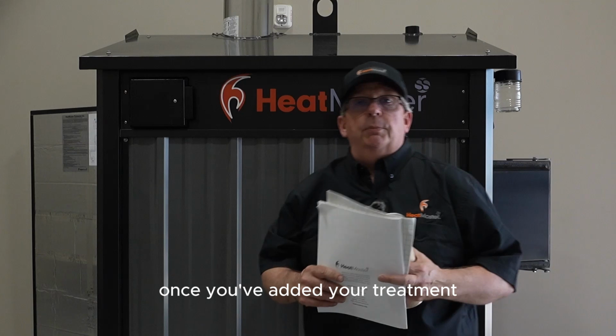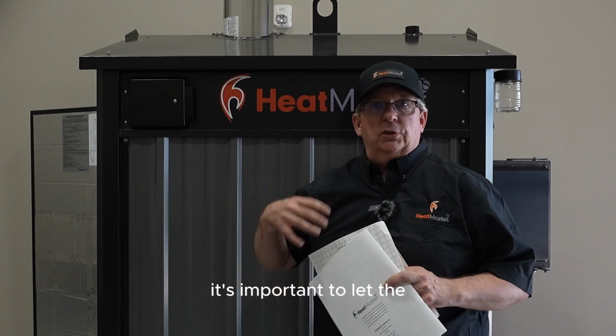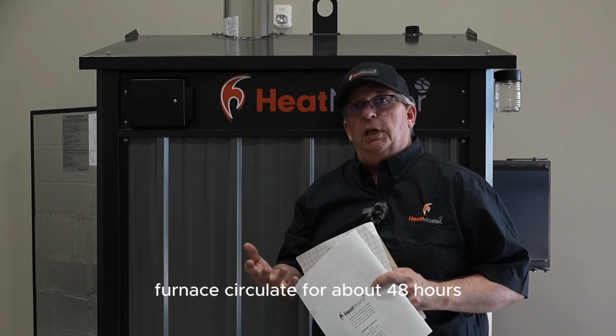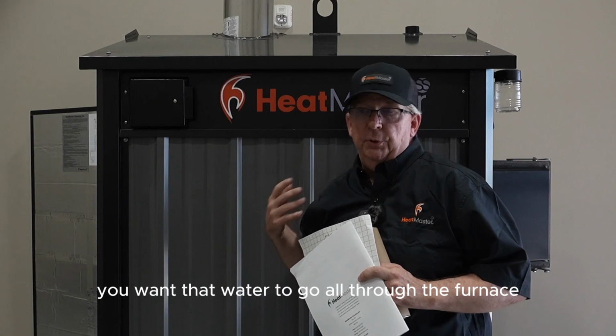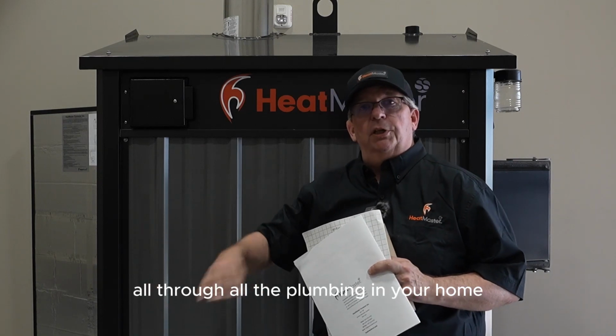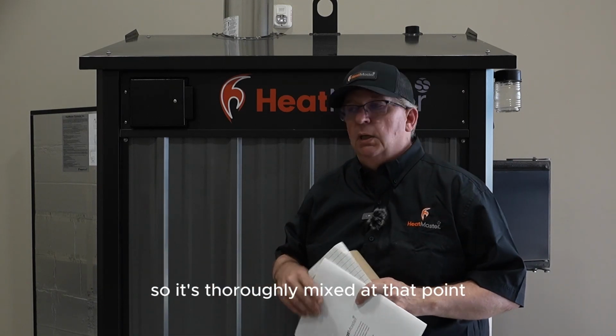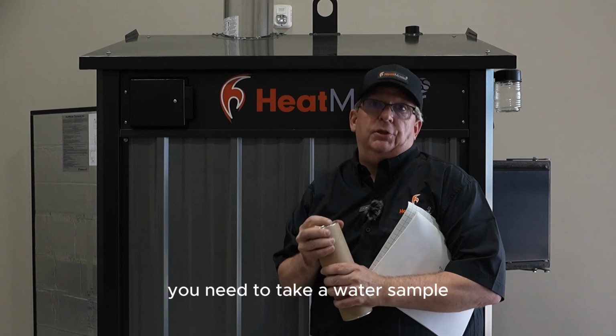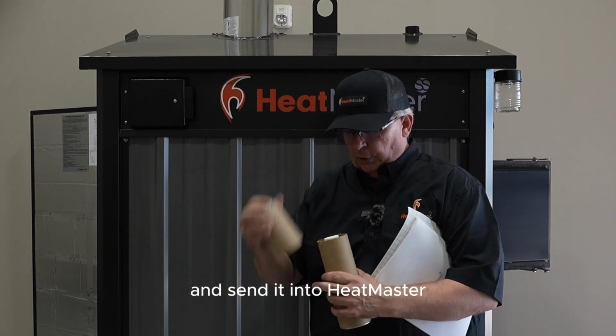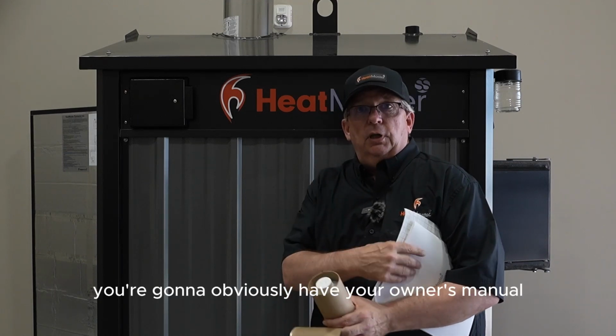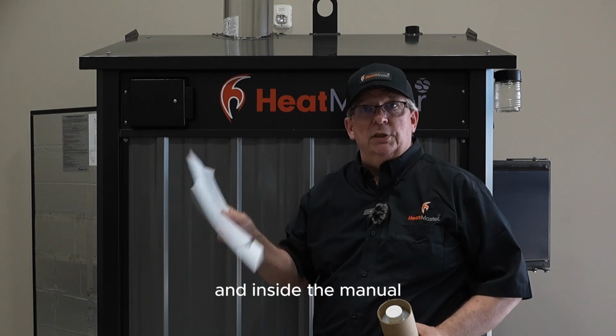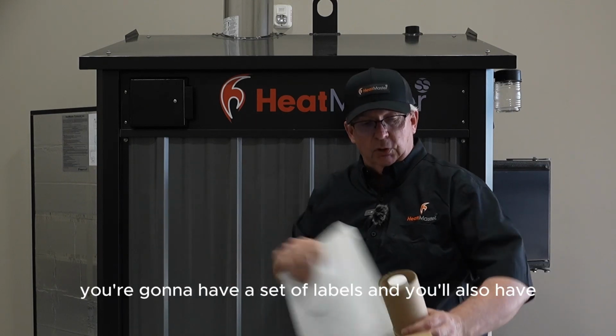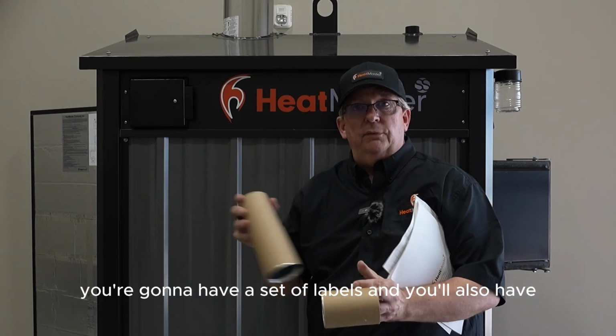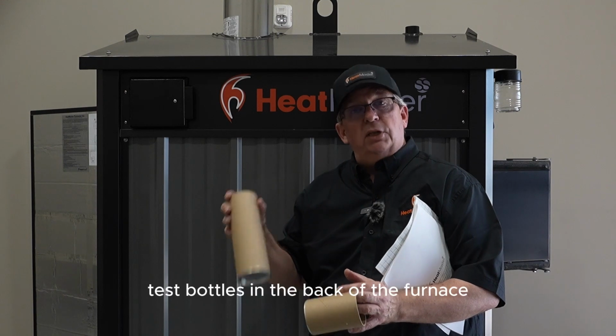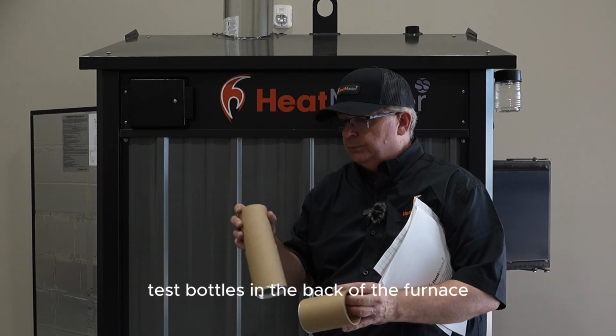Once you've added your treatment, it's important to let the furnace circulate for about 48 hours. You want that water to go all through the furnace, all through all the plumbing in your home so it's thoroughly mixed. At that point, you need to take a water sample and send it into Heatmaster. So with your furnace, you're going to obviously have your owner's manual, and inside the manual, you're going to have a set of labels, and you'll also have 4 test bottles in the back of the furnace.